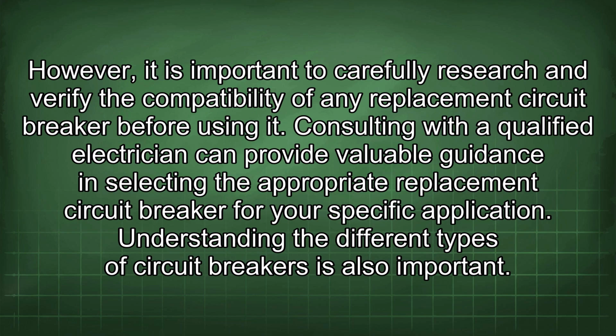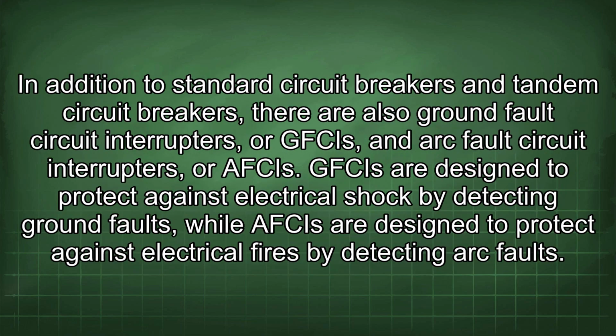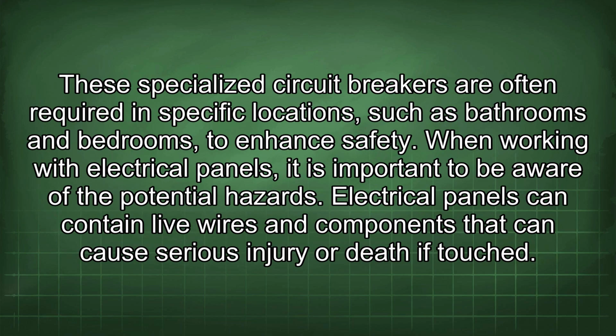Understanding the different types of circuit breakers is also important. In addition to standard circuit breakers and tandem circuit breakers, there are also ground fault circuit interrupters, or GFCIs, and arc fault circuit interrupters, or AFCIs. GFCIs are designed to protect against electrical shock by detecting ground faults, while AFCIs are designed to protect against electrical fires by detecting arc faults. These specialized circuit breakers are often required in specific locations, such as bathrooms and bedrooms, to enhance safety.